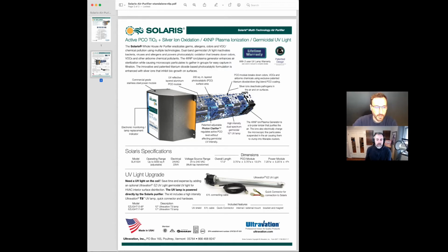Yeah, I totally agree, Ron. As you can see, you're just sharing there on this literature, it's 12-inch or 17-inch options. And I think the most popular one I see out there is a 17-inch long lamp. The goal of UV, right, is time and intensity. So if we could fit the biggest bulb in there, that gives us more exposure of UV for that time and intensity goal.